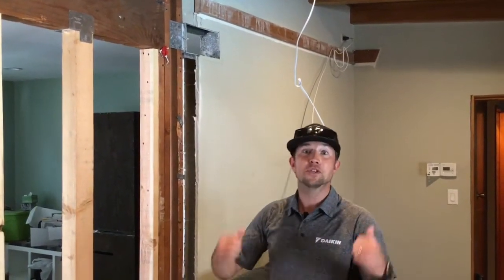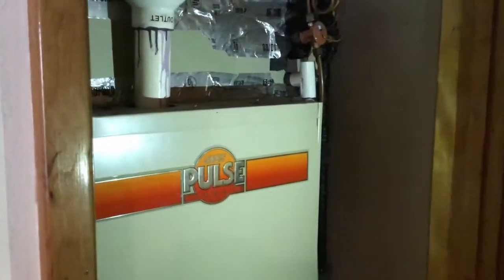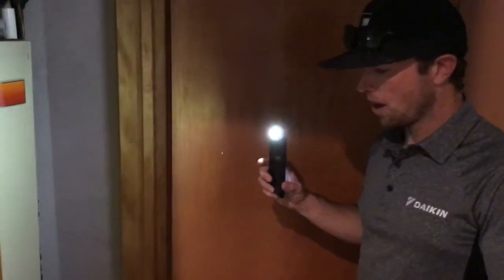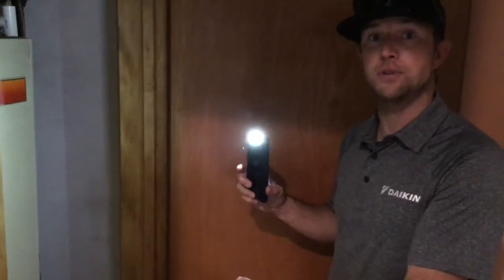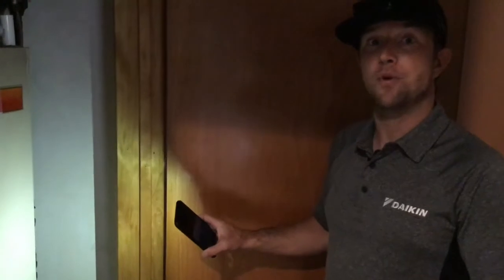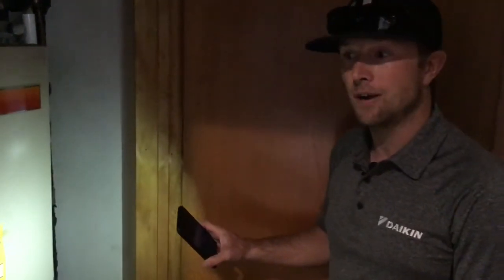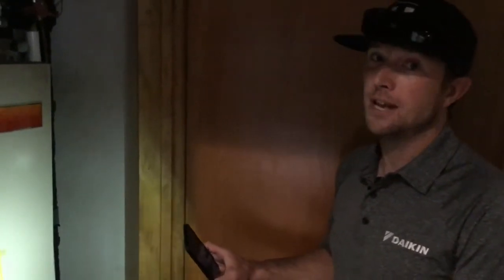Right now while we're here, let's check out the furnace in the closet. We've got a nice large furnace and everything was pretty well sealed up, but this isn't something that we are working on today — this is a product of somebody else's install. Our job is to make sure that every ounce of airflow that this thing produces, we have calculated and assigned a numerical value to it, and we're going to make sure we deliver enough airflow so that this thing is never starved for air and we squeeze every bit of efficiency out of this old furnace.